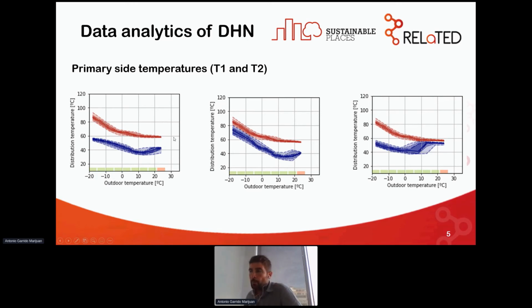But in the rest of the graphs, in the middle and on the right, there are problems, and we found these problems thanks to automatic inspection of the data. In this case, the cooling is not as expected, as planned by the operator, because it's lower than 20 degrees. And on the milder part of the heating curve, the response curve was not as expected.